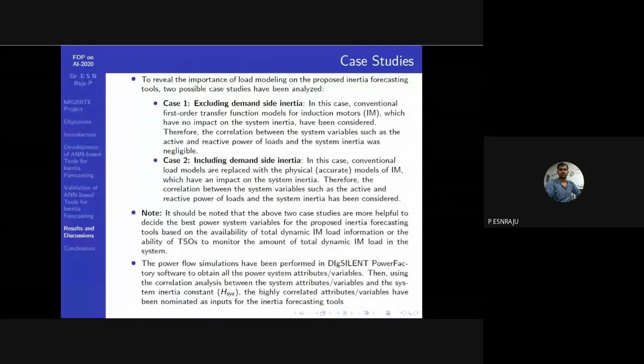In the development procedure, first we need to do power flow simulations. We utilized the DIgSILENT PowerFactory DPL code and performed the power flow simulations, capturing data on power system variables like active power, reactive power, voltage angles, and voltage magnitudes for all 4 replacement scenarios as well as the 2 case studies.